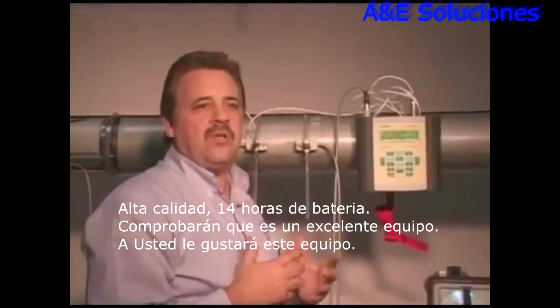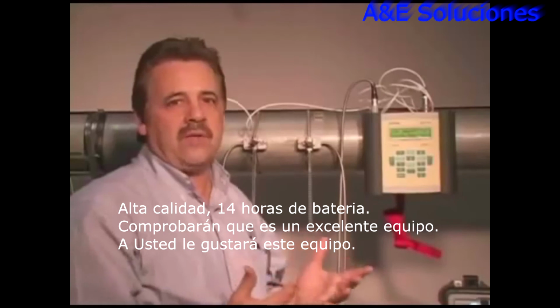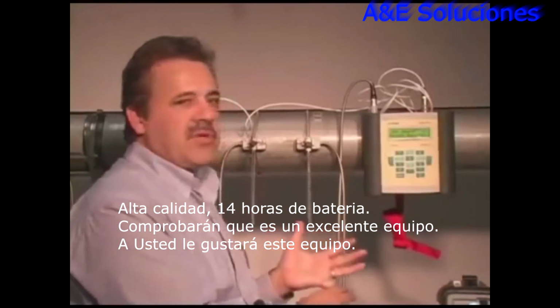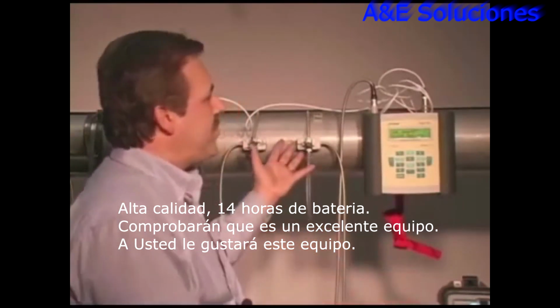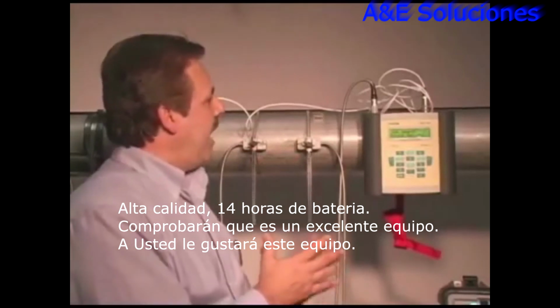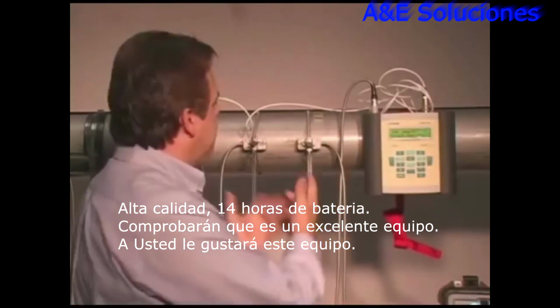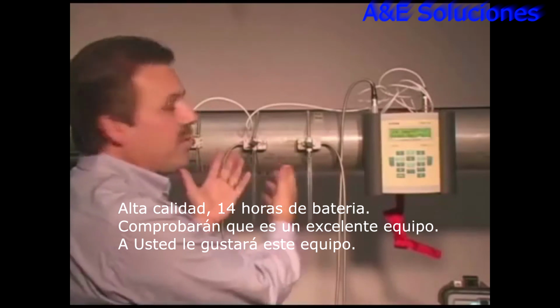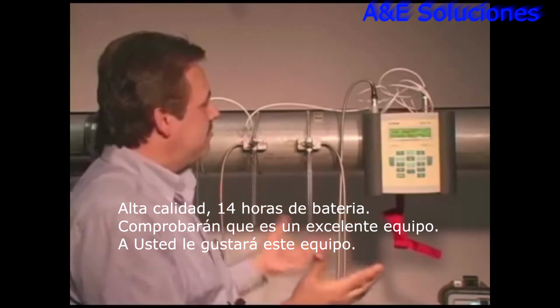But for the most part, the parts of the menu that you need to use with the meter are really quite simple. You go into parameters, you tell it your pipe information, liquid, and then you go to measure. It tells you what distance to put the transducers. You install them, and you've got your reading.